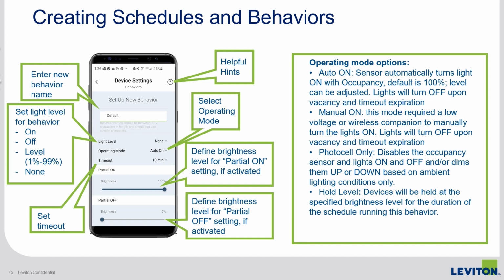For lighting based on occupancy, you can also select partial on and partial off levels, including a timeout for the partial off level to go fully off. When vacant, if you want the lighting to go to the partial off level and stay there, select that as an option in the app. Next is level. Like partial on, when the behavior starts, the lights will automatically go to this level. This can be anywhere from 1 to 99%.